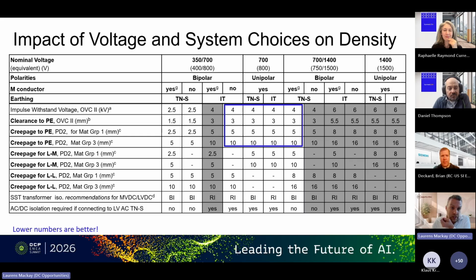Then there's another aspect, and that is the density, and that's one of the main drivers for DC in data centers, the volumetric density to get more compute power in the rack. And here what we see is that as we go up in voltage, you need more space to make sure that everything is safe. And it's mainly the space towards your enclosure that is having a big impact here. And you see the first 2 systems, they have the lowest clearances because they have a very low voltage to ground, only 350 volts nominal. If you leave your system floating, you need to design for the worst case.